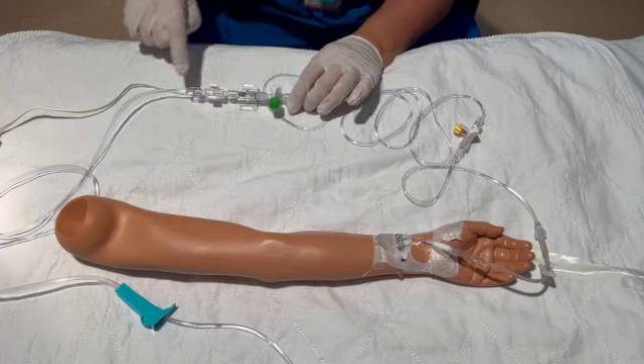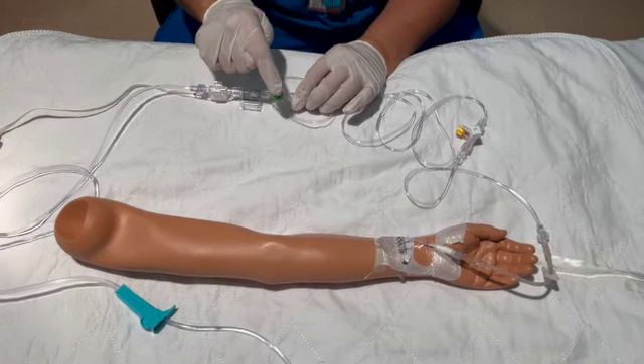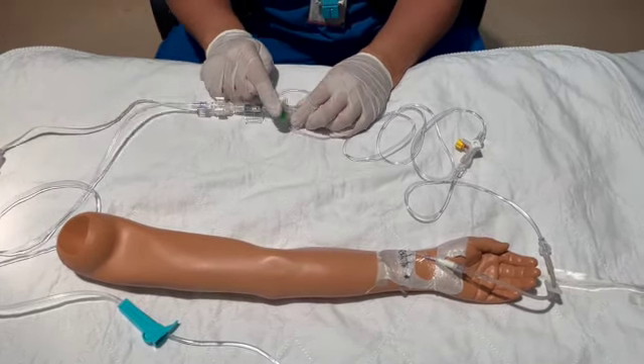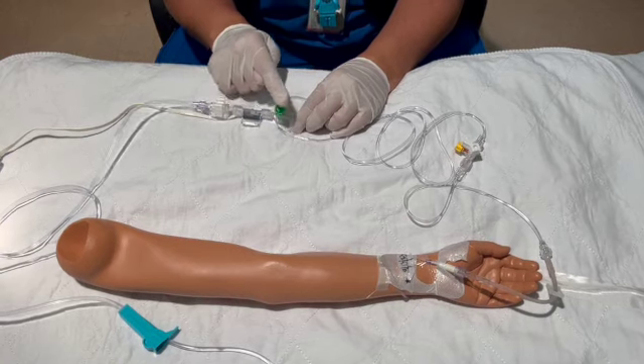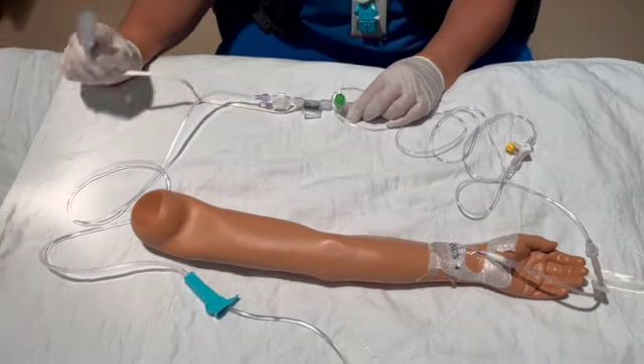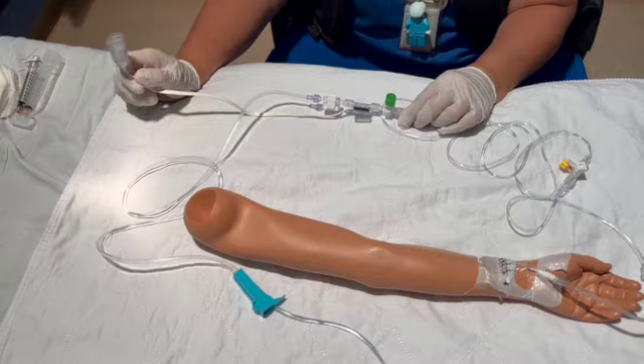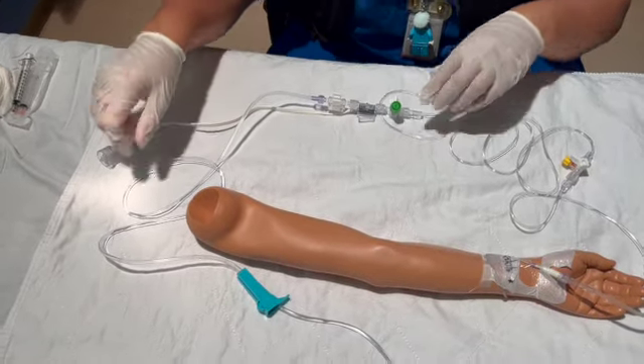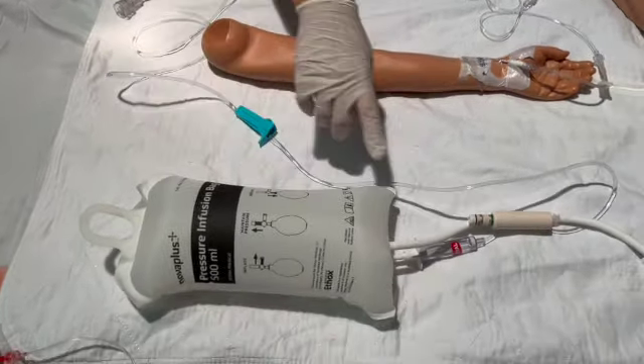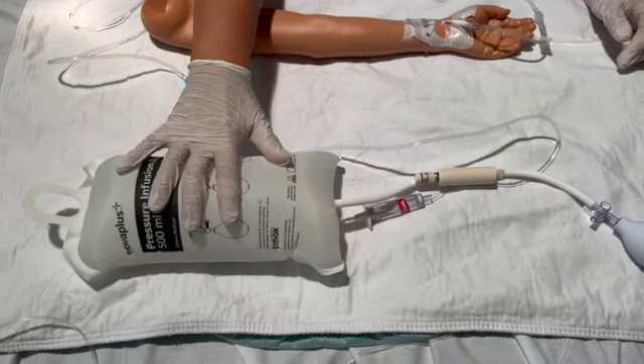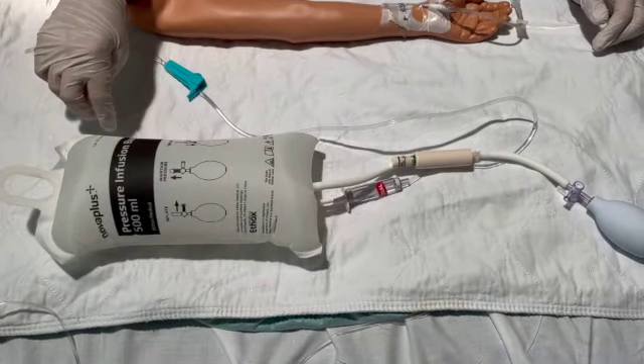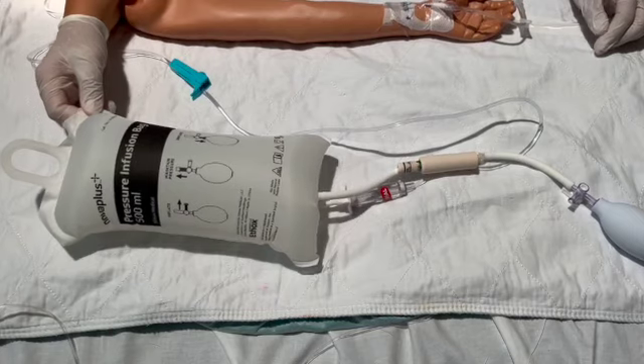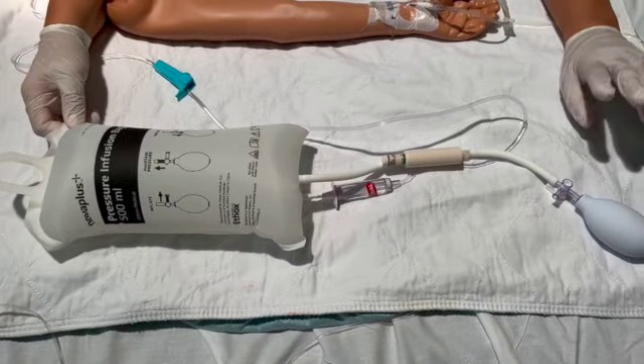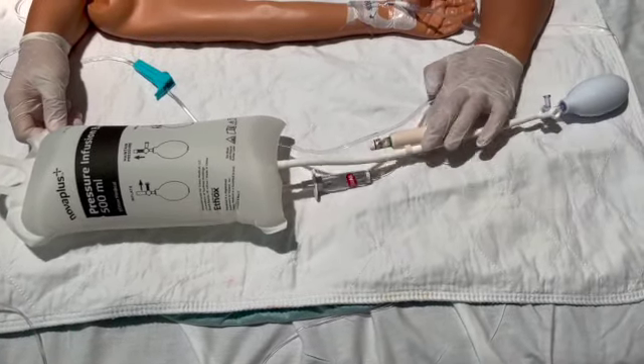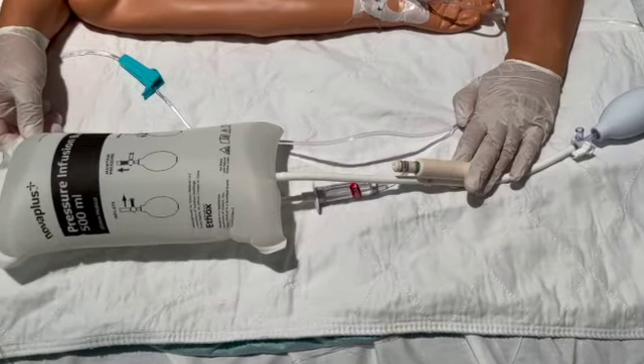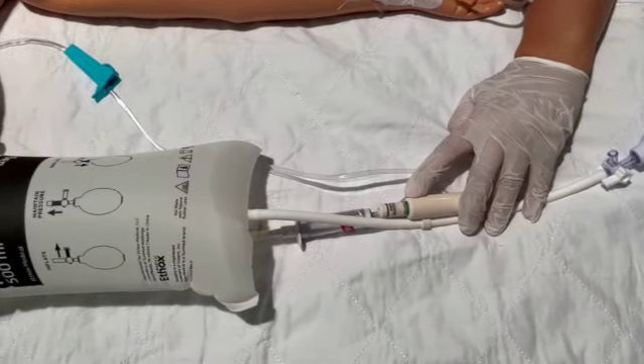This is the actual transducer. This particular port is capped off, but we're going to add a normal saline syringe to that. The cord is going to be hooked up to your monitor. And you have your transducer bag, which is a 500 cc bag of normal saline, pumped up on the pressure bag to 250 millimeters of mercury, which is a green mark on the bag.